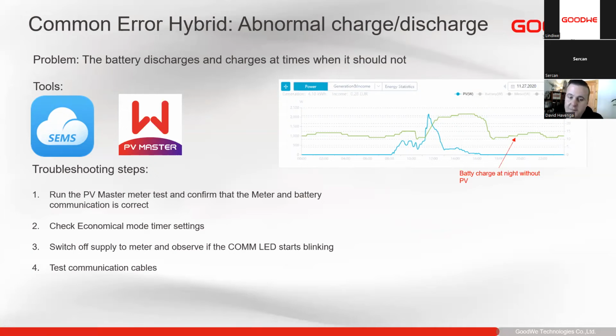We can check if the customer has maybe set an economical mode timer. We can switch off the supply to the meter and observe the COM LED to see if it starts flashing. And then lastly, we can check the communication cables.